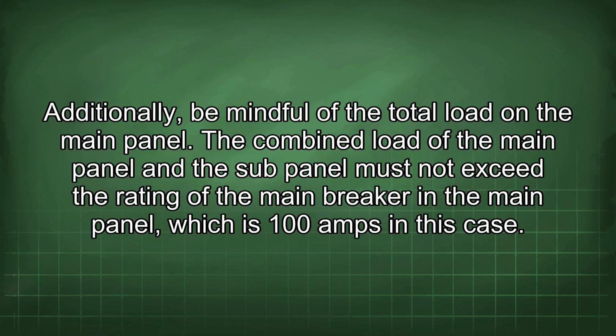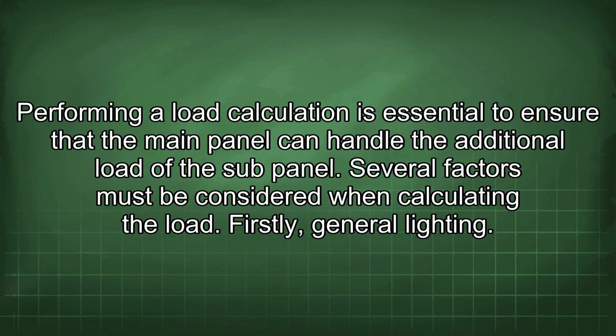Additionally, be mindful of the total load in the main panel. The combined load of the main panel and the sub-panel must not exceed the rating of the main breaker in the main panel, which is 100 amps in this case. Performing a load calculation is essential to ensure that the main panel can handle the additional load of the sub-panel. Several factors must be considered when calculating the load.